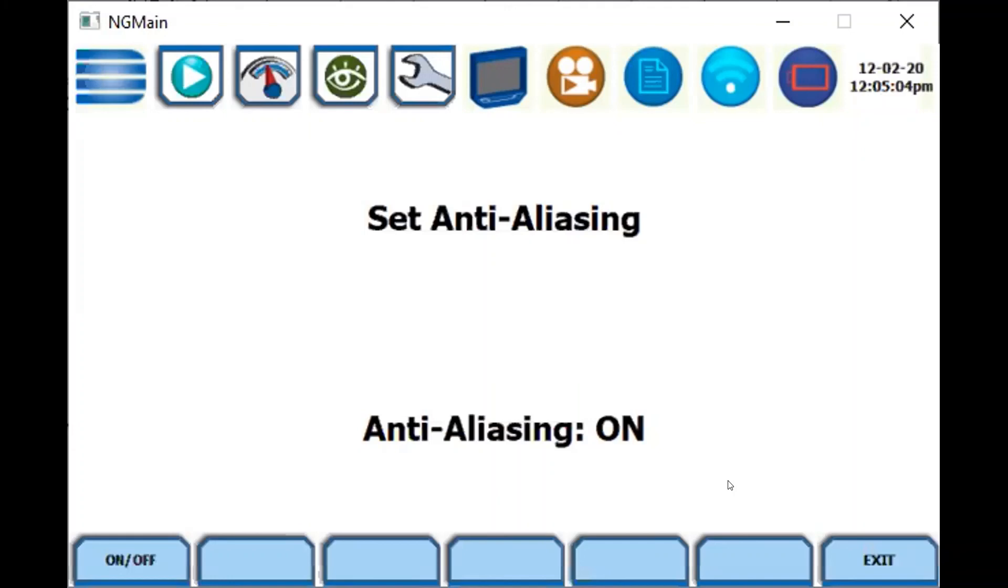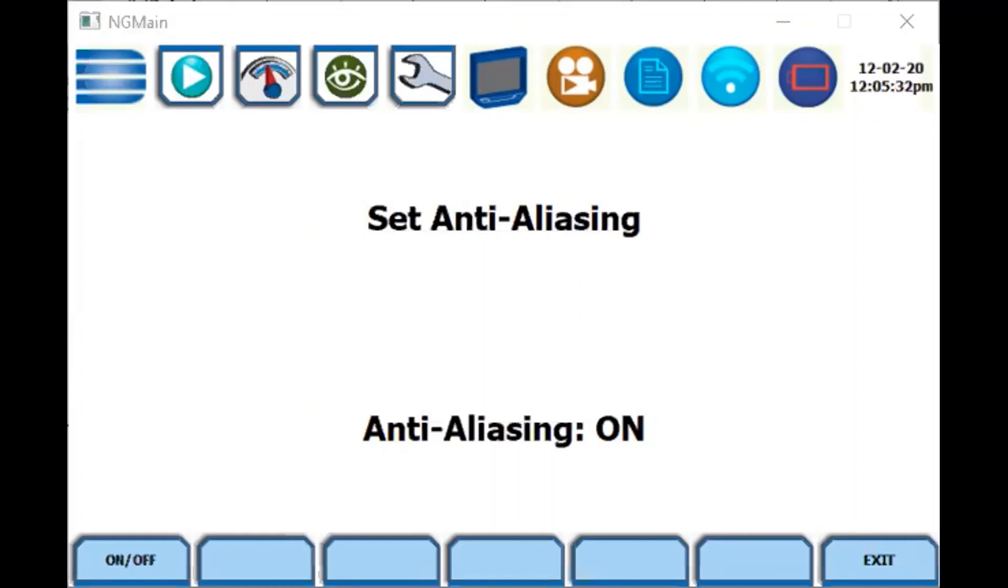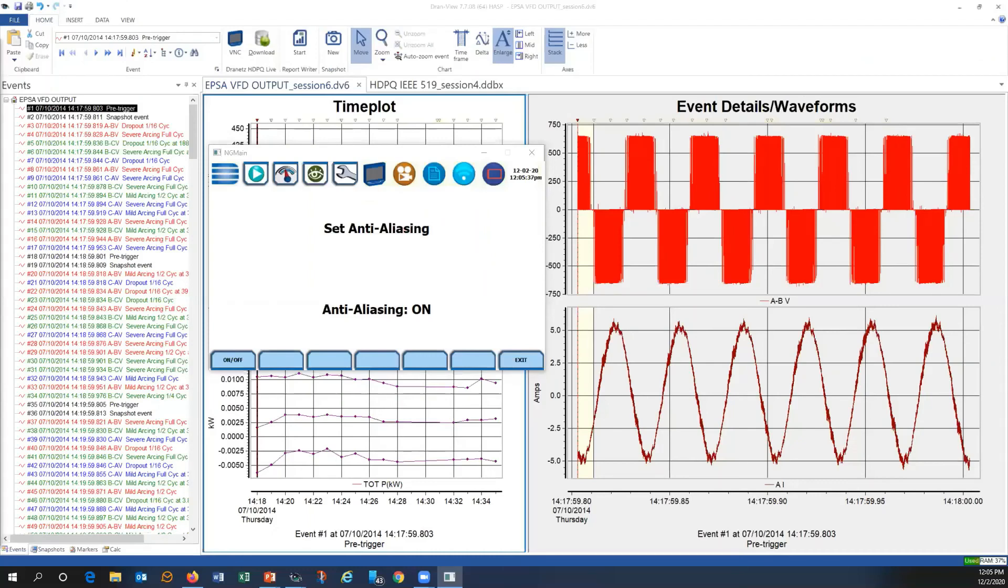The reason we have these filters is they're required for IEC 61000-4-30 class A edition three compliance. They default to off because these filters tend to filter out transients and other high speed information. But to be fully 100% compliant with the standard, the edition three standard, you should have anti-aliasing on. We do recommend this for VFD application - there is another benefit of filtering out a lot of the switching noise from the VFD. Let me go back to share Dranview, and then we will review the questions here.